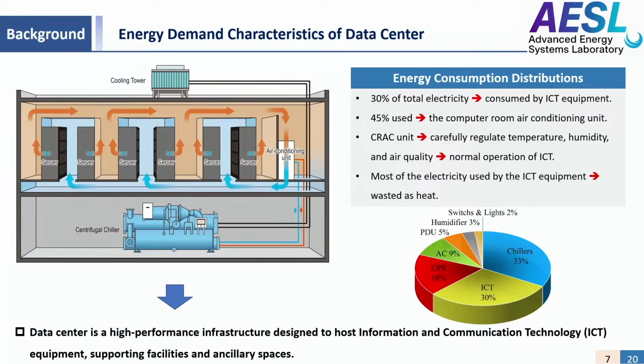In a data center, approximately 30% of total electricity is consumed by information and communication equipment, while nearly 45% is used by the computer room air conditioning unit, which includes chillers, humidifiers, and distribution systems such as fans and water pumps. The computer room air conditioning unit carefully regulates the temperature, humidity, and air quality inside a data center for the normal operation of information and communication technology equipment.